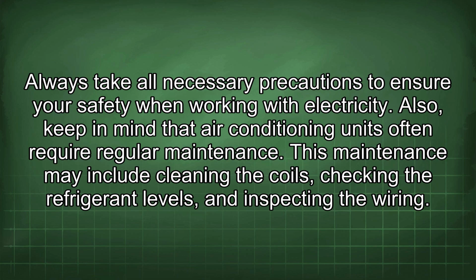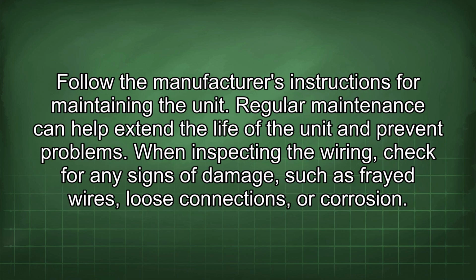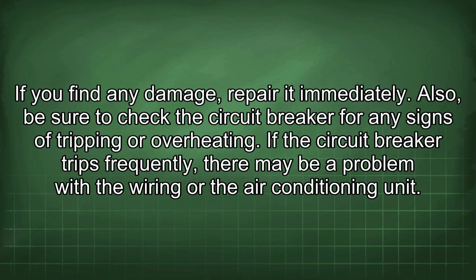Also, keep in mind that air conditioning units often require regular maintenance. This maintenance may include cleaning the coils, checking the refrigerant levels, and inspecting the wiring. Follow the manufacturer's instructions for maintaining the unit. Regular maintenance can help extend the life of the unit and prevent problems. When inspecting the wiring, check for any signs of damage, such as frayed wires, loose connections, or corrosion. If you find any damage, repair it immediately.